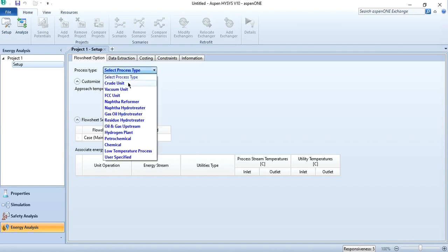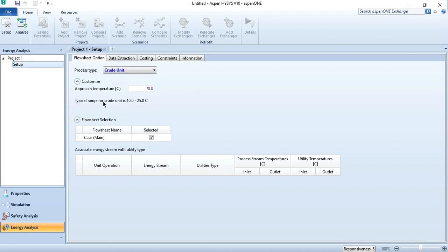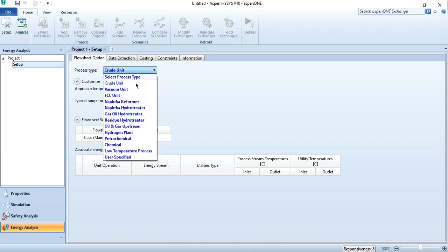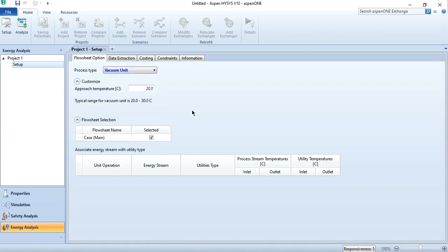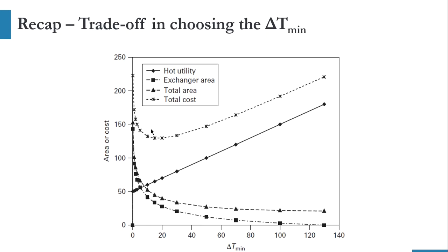For example, if it's a crude unit, you can see the typical range — the approach temperature is 10 to 25 degrees centigrade. Similarly, for the vacuum unit, this value may vary from 20 to 30. If you remember our previous exercise, we had discussed a chart — which is this one — and we had selected the range of 10 to 20 degrees centigrade.